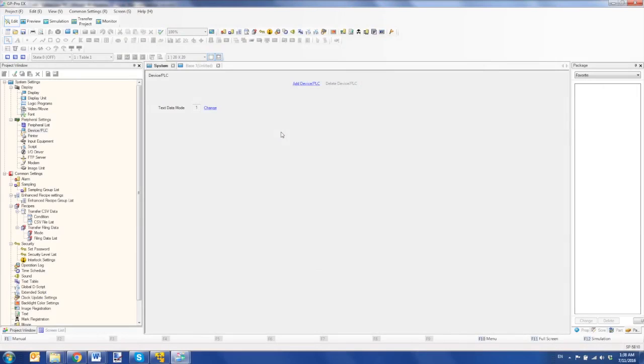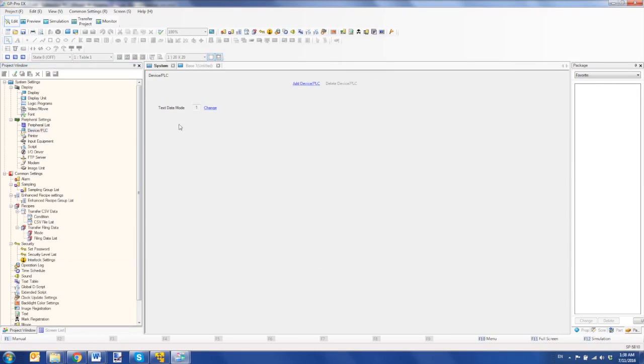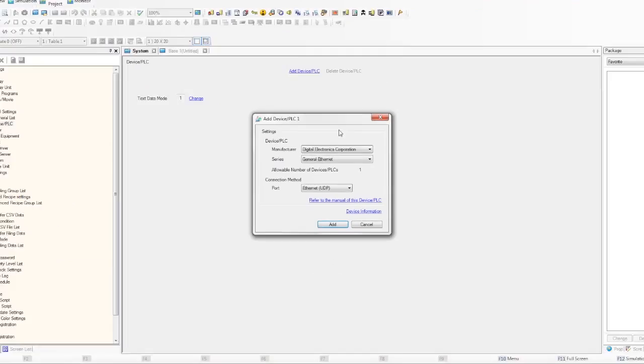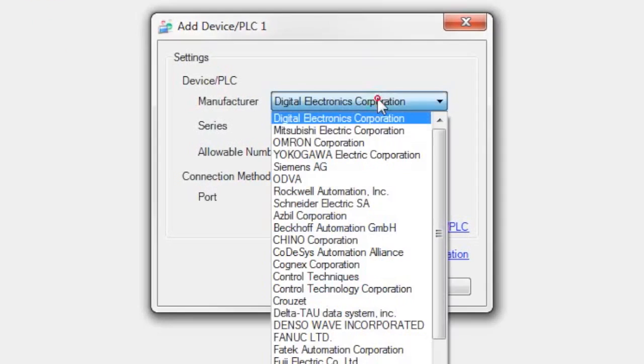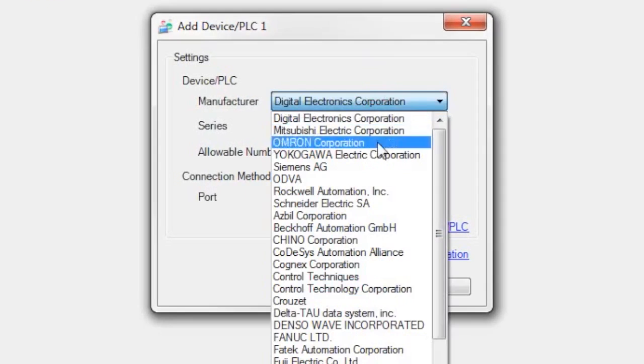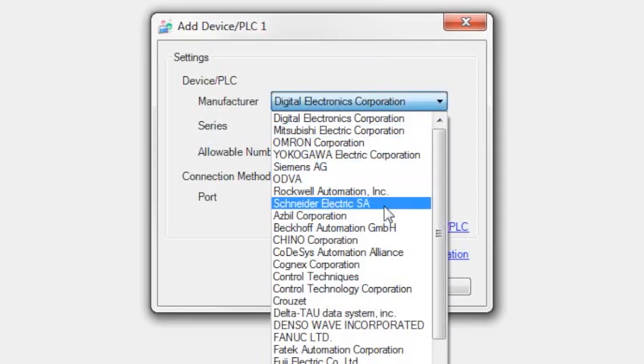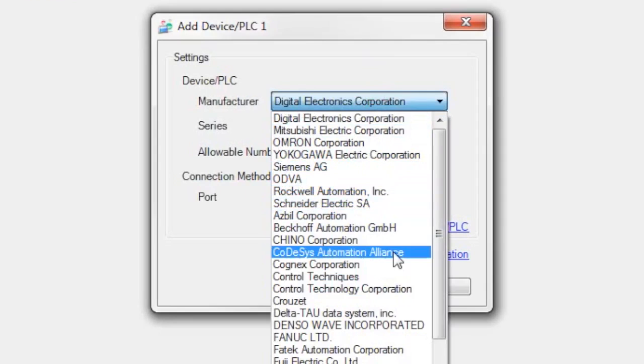In order to connect a Modicon machine structure PLC from Schneider Electric to a ProFace HMI, you would in the GP Pro EX software select Device PLC from peripheral settings, add a device, and you would select one of two things: Schneider Electric or CoDeSys.